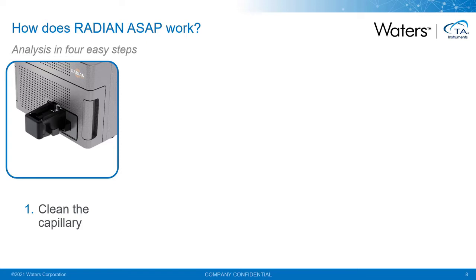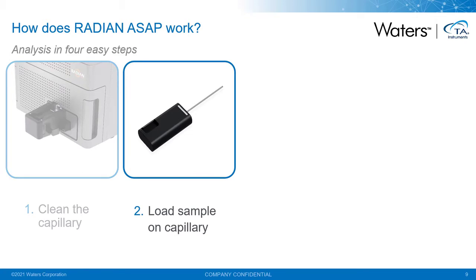The first step is to clean the capillary to remove any background material which may have been picked up from the packaging or from handling. To do this, you simply load the capillary into the system and use the dedicated bakeout button in the software. This automatically heats the capillary to 600 degrees centigrade for one minute, increases the gas flow, and raises the corona current to remove any contaminants which may give background ions in your analysis.